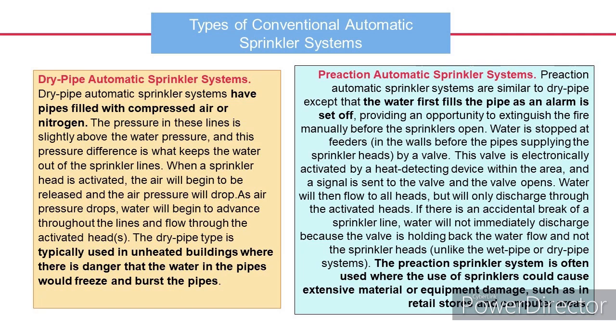Water will then flow to all heads, but will only discharge through the activated heads. If there is an accidental break of a sprinkler line, water will not immediately discharge because the valve is holding back the water flow and not the sprinkler heads, unlike the wet pipe or dry pipe systems. The pre-action sprinkler system is often used where the use of sprinklers could cause extensive material or equipment damage, such as in retail stores and computer areas.